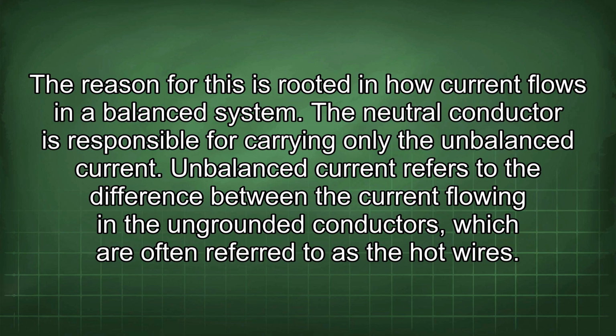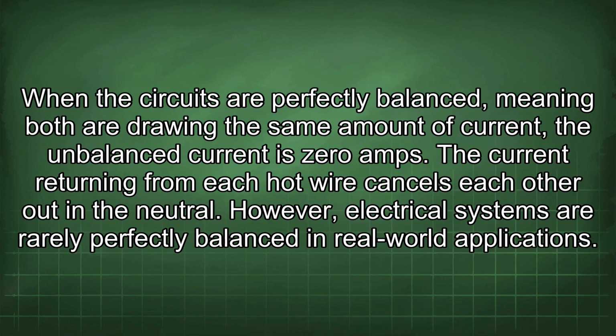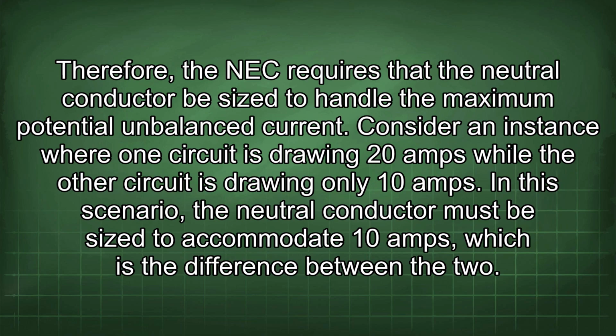Unbalanced current refers to the difference between the current flowing in the ungrounded conductors, which are often referred to as the hot wires. When the circuits are perfectly balanced, meaning both are drawing the same amount of current, the unbalanced current is 0 amps. The current returning from each hot wire cancels each other out in the neutral. However, electrical systems are rarely perfectly balanced in real-world applications. Therefore, the NEC requires that the neutral conductor be sized to handle the maximum potential unbalanced current.